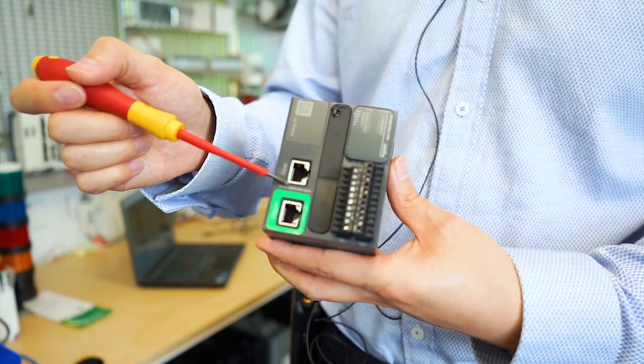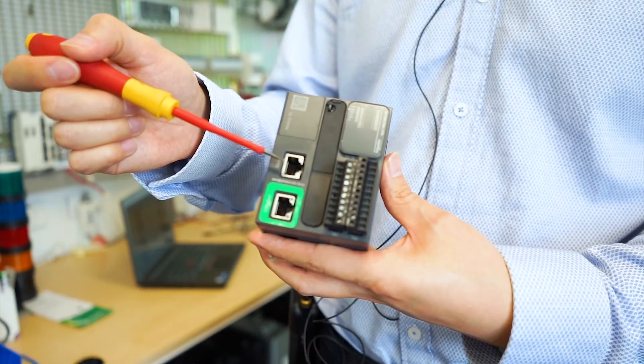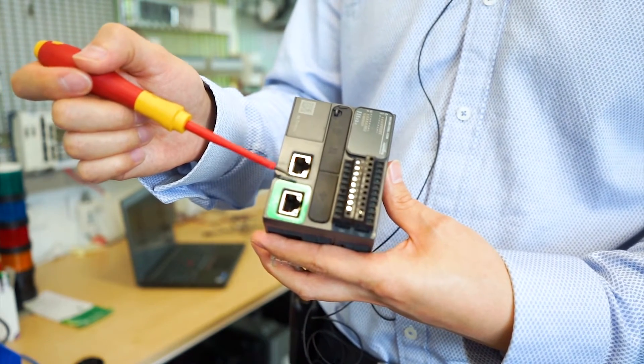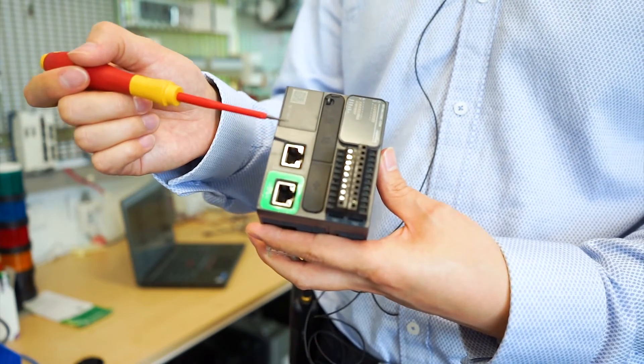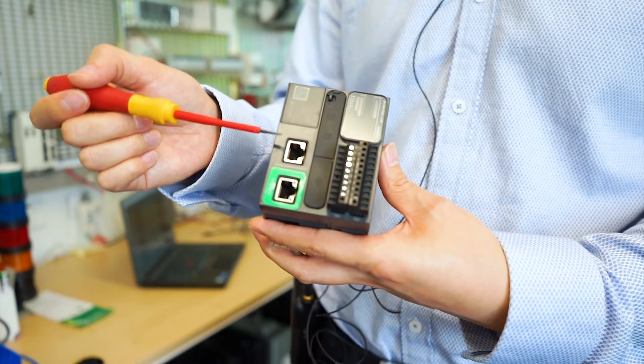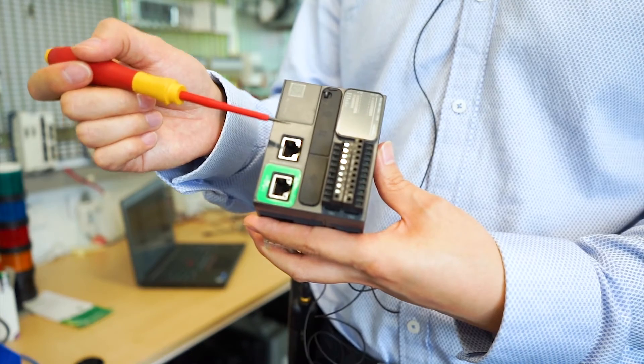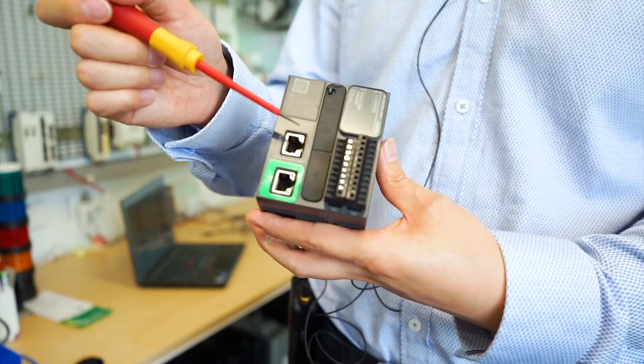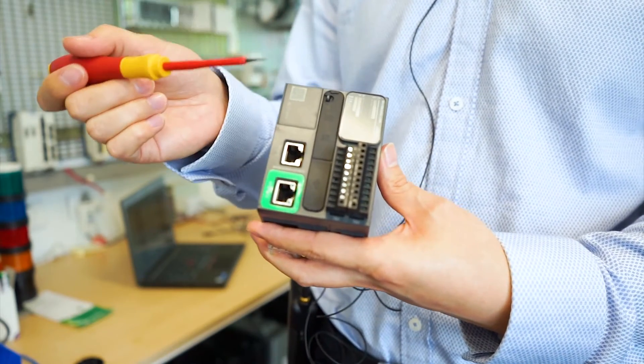As you can see, we have this MAC address. The default IP address with one, two, three, four, five, six - six part hexadecimal numbers. The default IP address will be 10.10 dot the last two hexadecimal numbers translated to the decimal number.